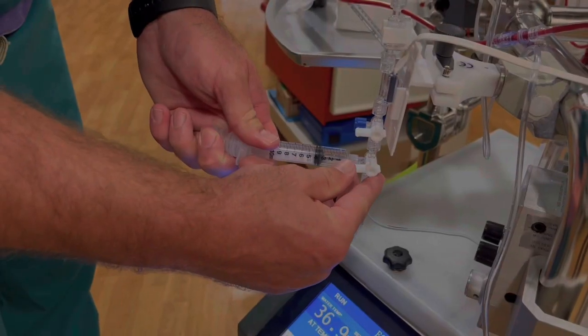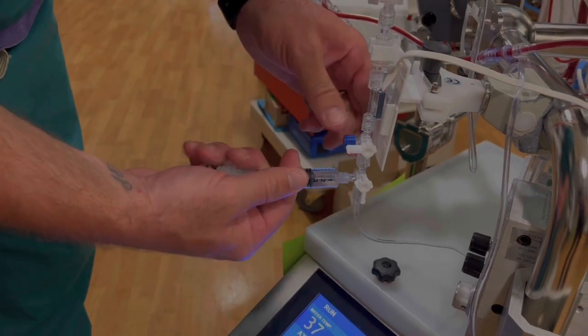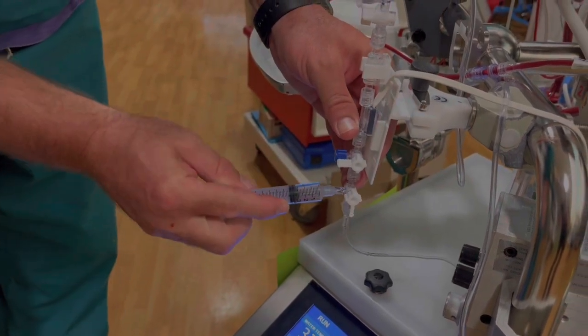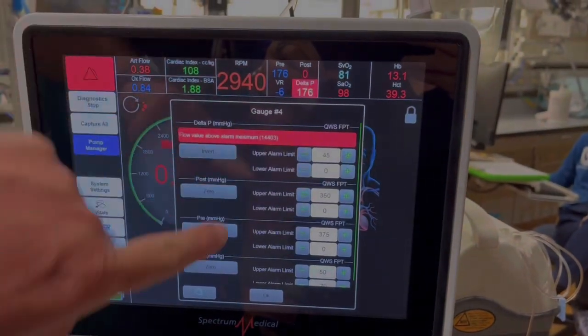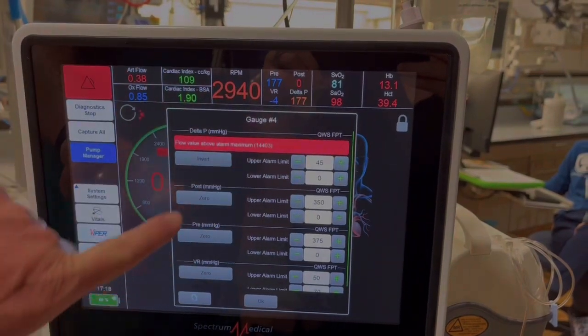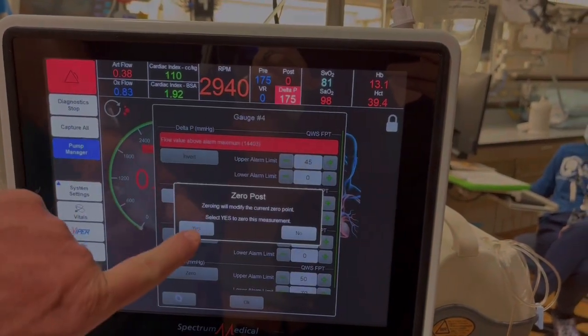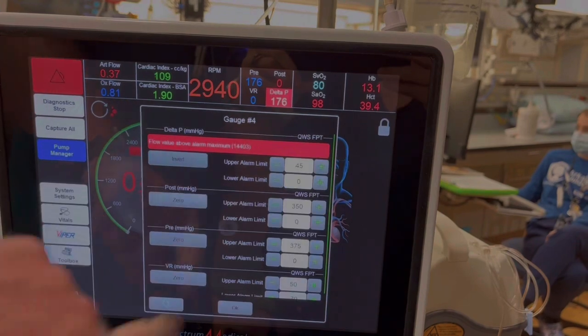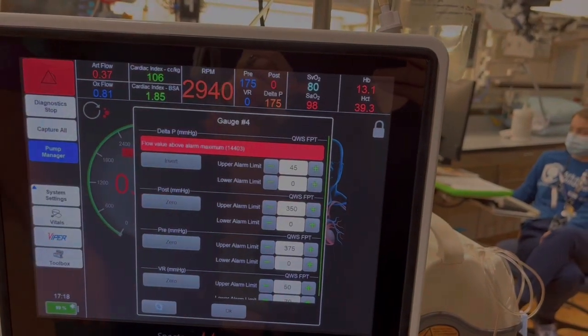Once the line is cleared, we're going to turn the stopcock down off to the circuit and open the transducer to atmosphere. Under the pressure section of the gauge bar, we're going to tap that to open up our zeroing options. Under the post-membrane tab, we're going to click 0 and then yes, and confirm that it has zeroed.